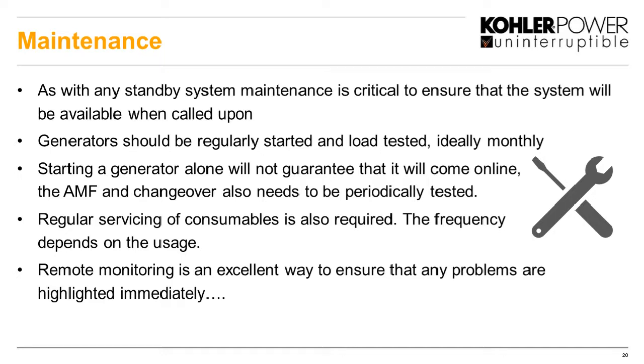The engine must be regularly serviced, as we would with our vehicles, and there are consumables required. Filter changes, oil changes, pipe changes. We can test the oil if it needs it, but that frequency depends on the usage of the standby set as well. So that actually can vary, but it is a very, very important thing that these are regularly serviced and tested, to make sure they come online.